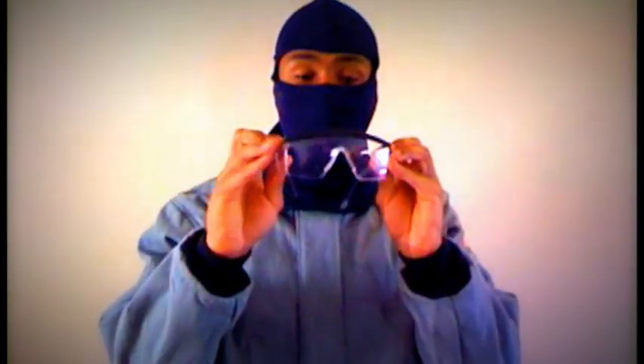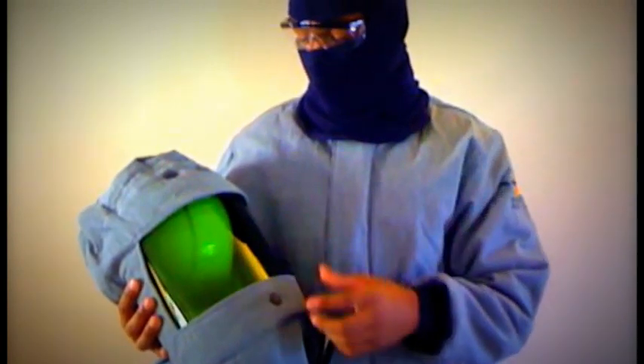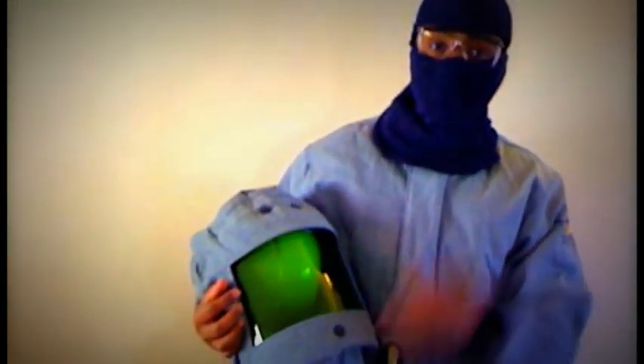Once you have those in, you have your safety goggles, which have to meet ASTM standards regarding the surface of the actual safety goggles. Then you'll put those directly over the balaclava. Make sure that they're securely fit. Then you have your face shield — the Arc Series, a 40 cal face shield with visual light transmission.